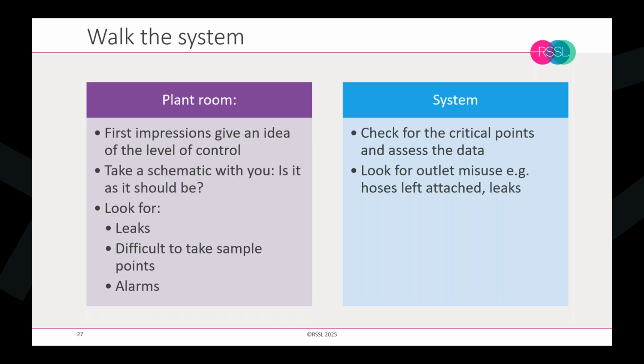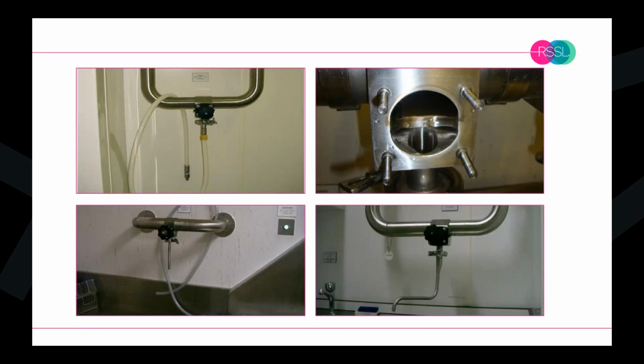It's useful to take into account difficult to reach sample points, particularly in the plant area. So if QC come along once a week and they have to clamber over pipes and various things, how can they take that sample in a hygienic way? And also to check, have there been any recent alarms, and how frequently are those alarms reviewed? And then when the actual system is looked at, the user outlets, you can call upon some critical points and ask to see the data trends for bioburden and for endotoxin, and also keep an eye out for poorly maintained hoses. And on that subject, we have some photographs here.